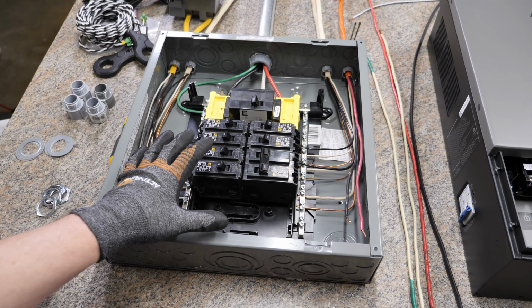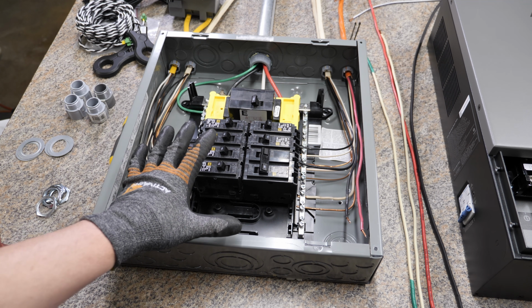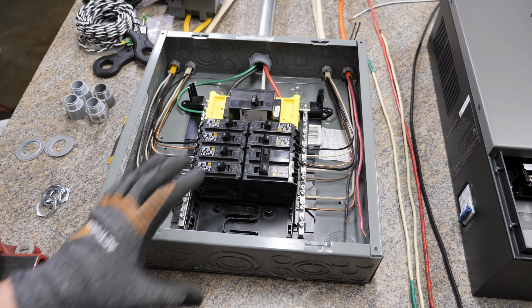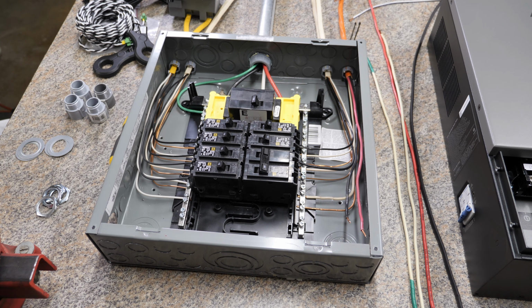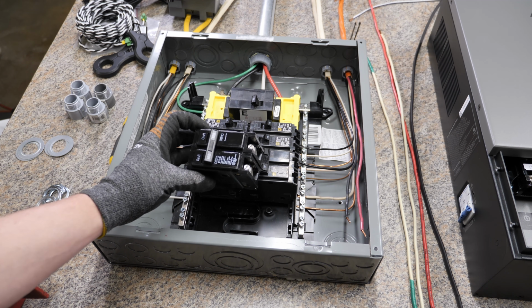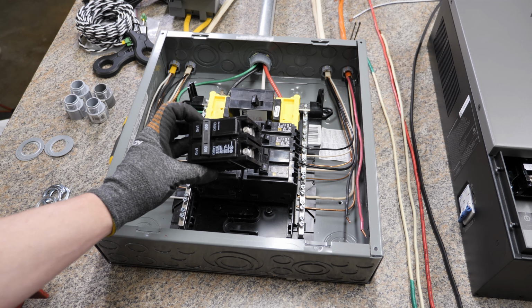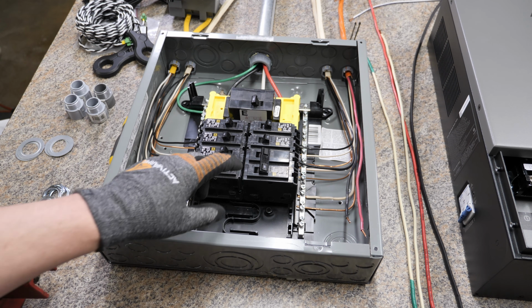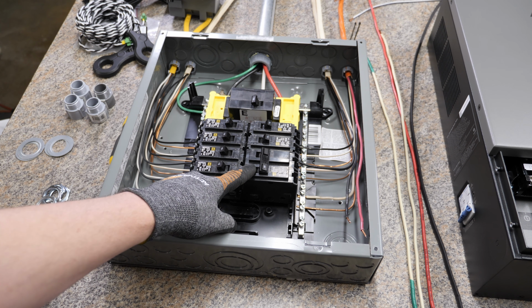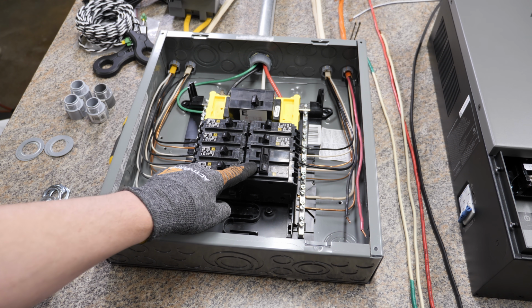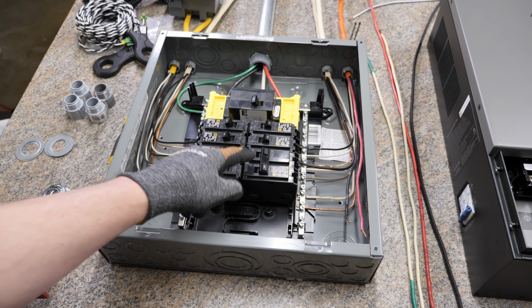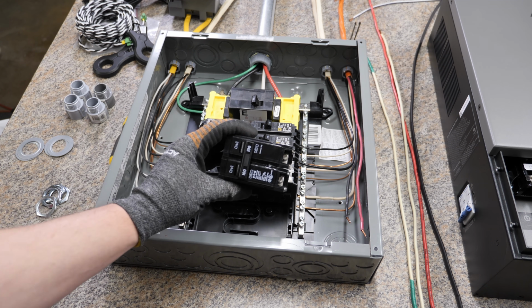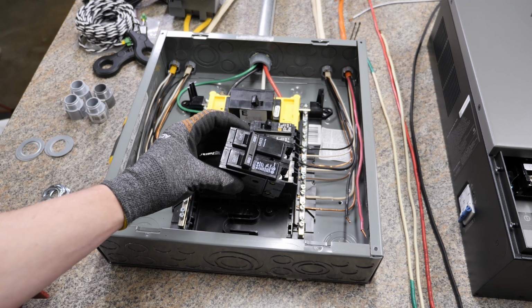First thing we have is our simulated main electrical panel in our house. One quick note: the supplied 100 amp double pole circuit breaker they sent doesn't actually go with this panel, so I'm going to use a 30 amp double pole circuit breaker I already had. But the kit does recommend using a 100 amp circuit breaker.